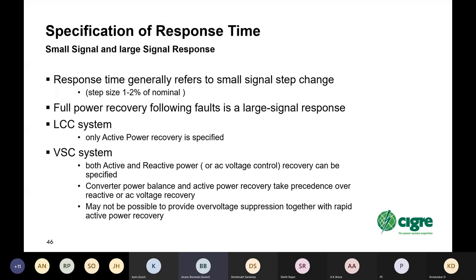Converter balance and power balance and reactive power recovery. Active power recovery usually takes precedence over reactive or AC voltage recovery. So when converter balance and active power recovery do take precedence, it may not be possible to provide overvoltage suppression together with rapid active power recovery. So the two may be mutually exclusive. So you have to decide which one should be prioritized and specify accordingly.